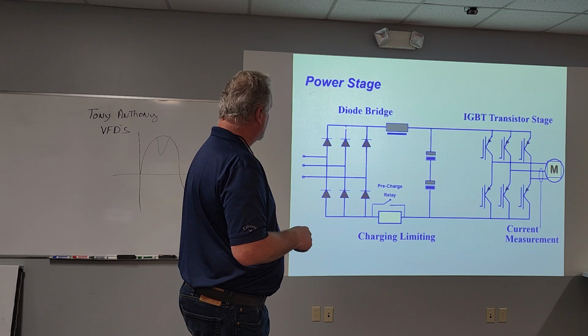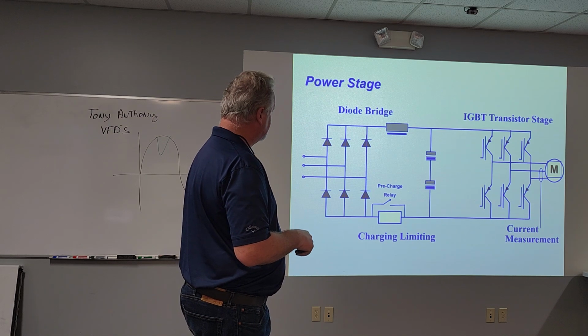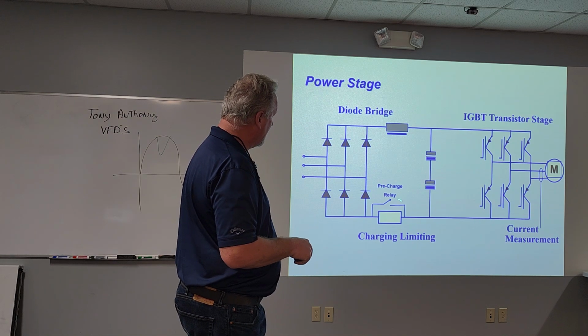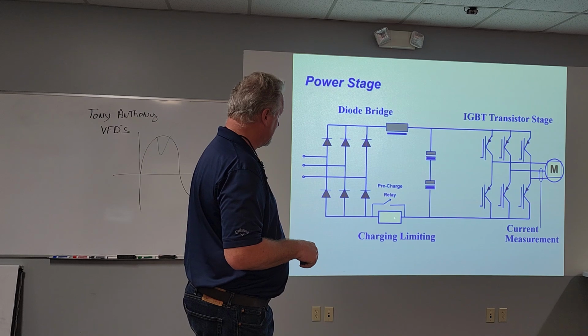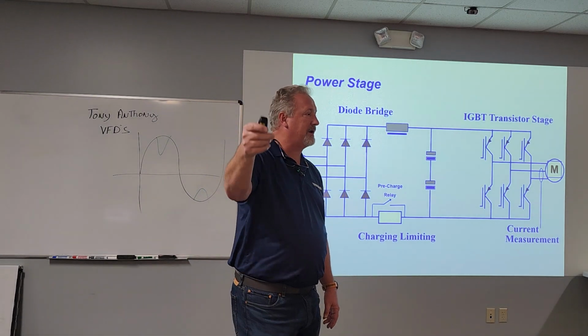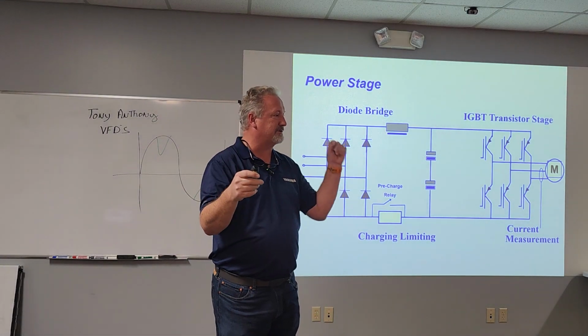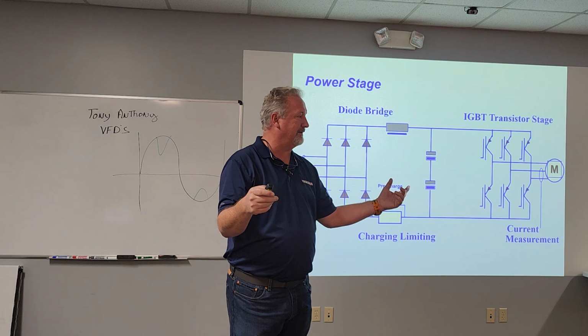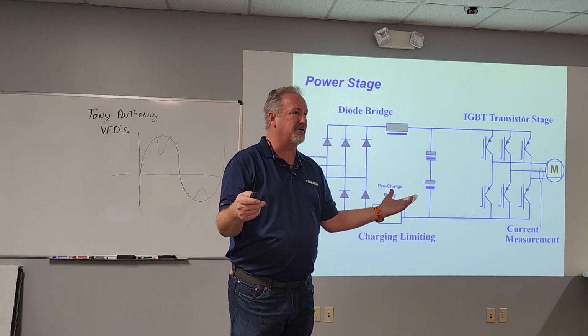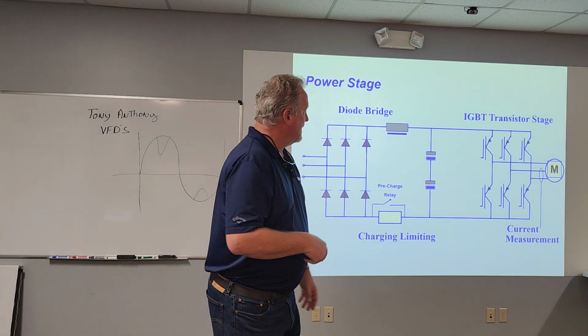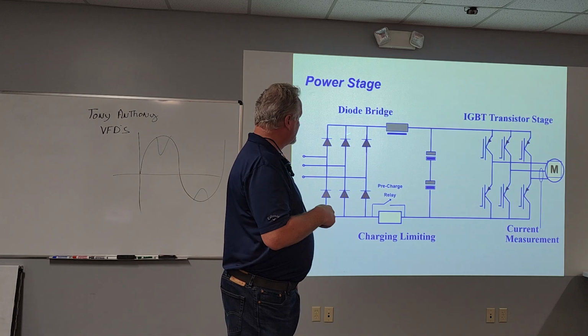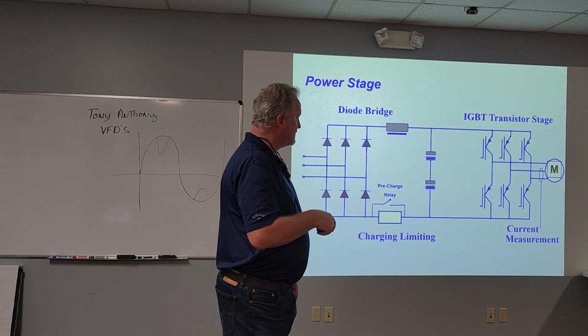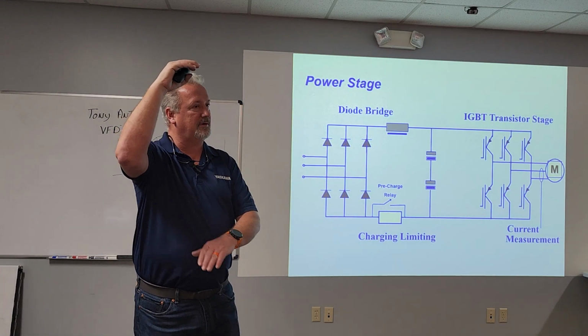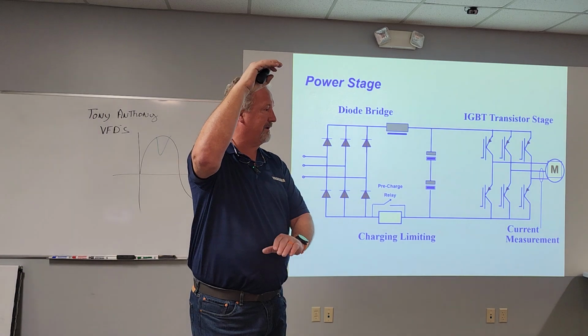First thing we have is the diode bridge. So this creates our DC bus. And then right here we have a pre-charge relay. You ever powered up a drive and like a half a second later you hear this big tonk, like a relay kick in? You'll notice they're usually on larger drives. And the reason we have that is we create this DC bus and we use capacitors to hold that DC bus, to develop it and hold it.